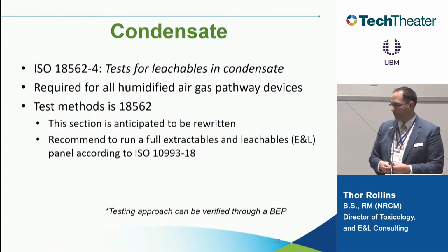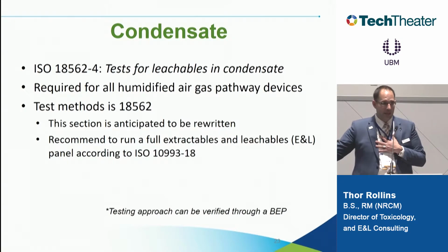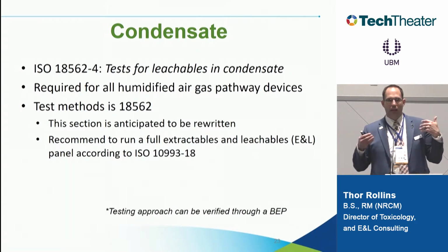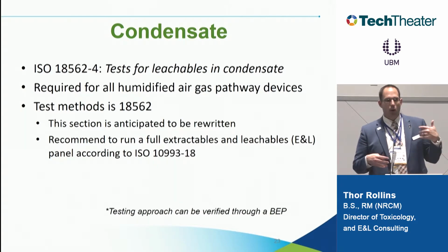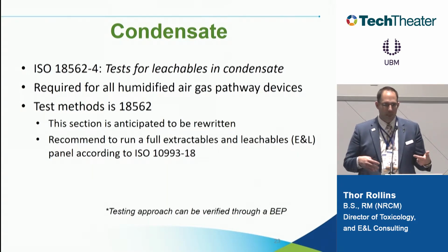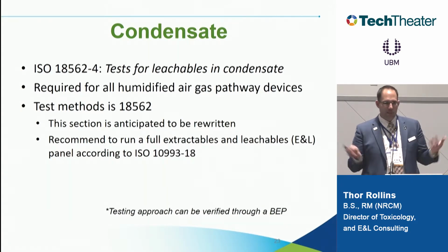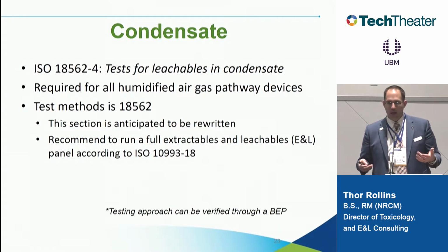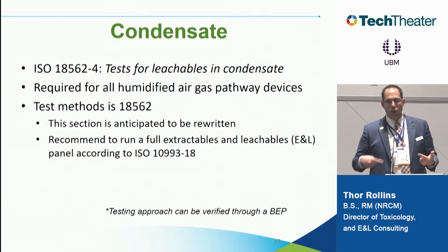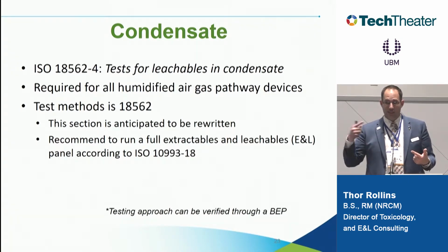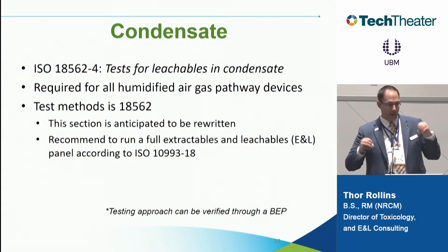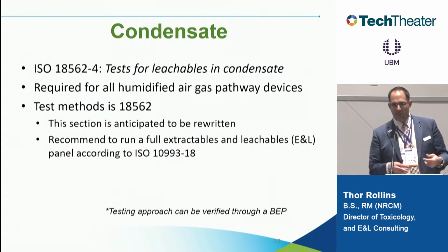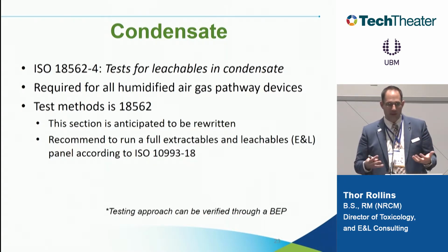This humidified air. What we recommend is a worst case approach. We recommend an extractable leachable test per ISO 10993-18. We don't recommend that you cut up your whole device and put it in there, because once again, that's not clinically relevant. We recommend running water through the gas or the humidified gas path to look at what comes off under the clinical conditions.